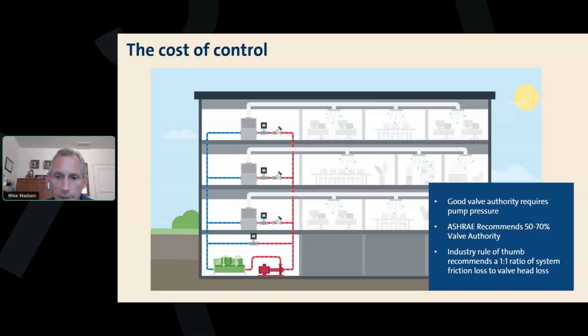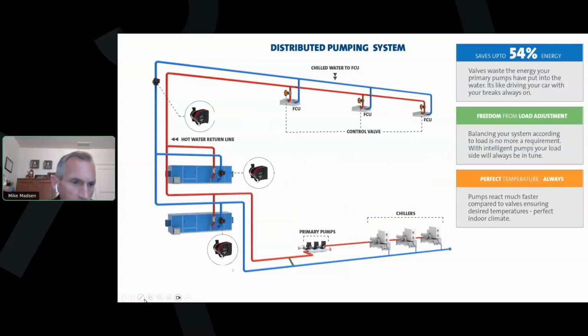So here we're seeing again, here's that primary pump skid we talked about. Here's the chillers. Here's the decoupler. And again, the primary pump skid has 2 jobs. The first job is to keep your chillers happy, and the second job is to keep chilled water available for the secondary pumps to pull from.